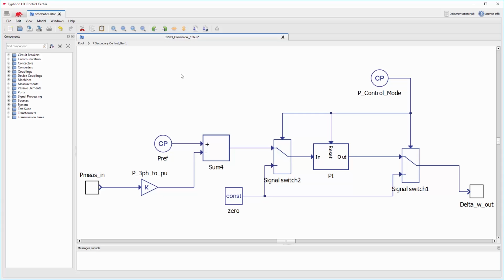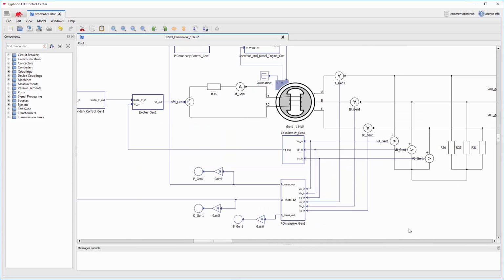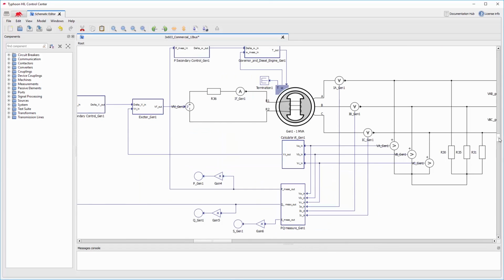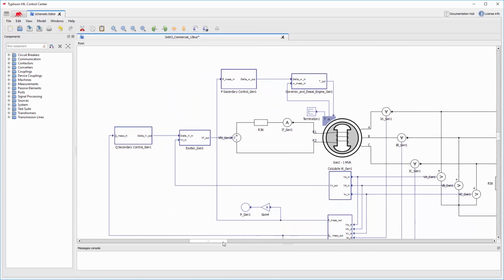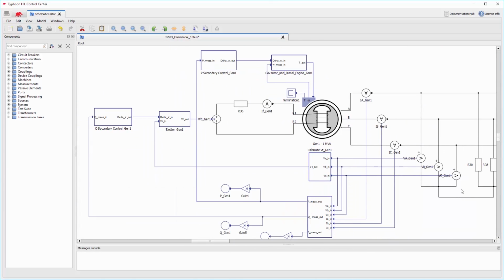With all these loops, the genset can be controlled in three modes: VF, in which the speed and voltage are precisely controlled. This mode is ideal for a standalone operation. PV, in which real power and voltage are controlled. As this control mode perturbs the reference speed, it can only be used to operate in grid connected. And PQ, in which real and reactive power are controlled. As the PV mode, this mode can only be used in grid connected operation.